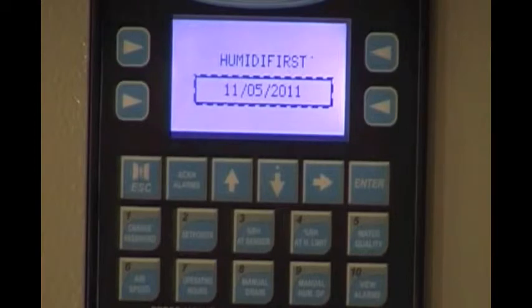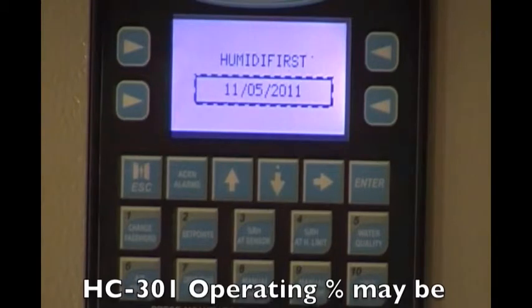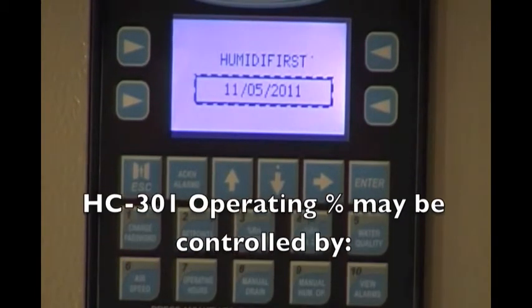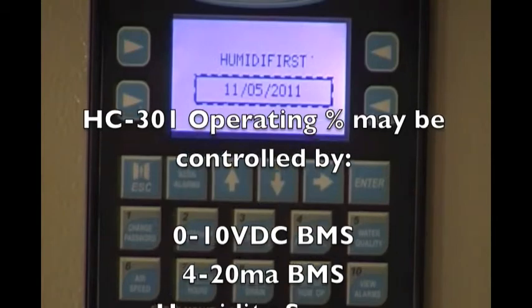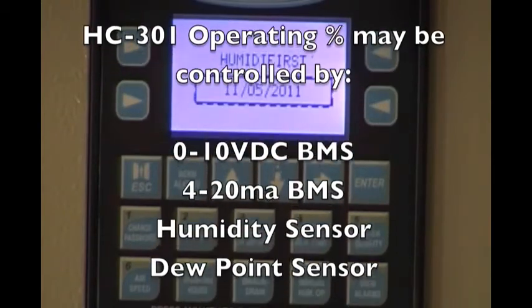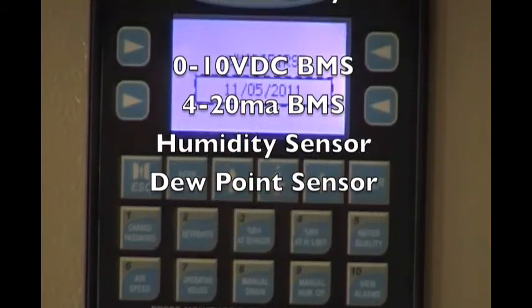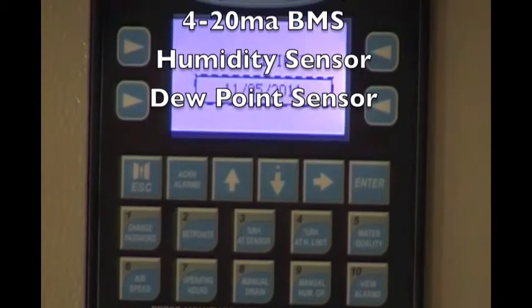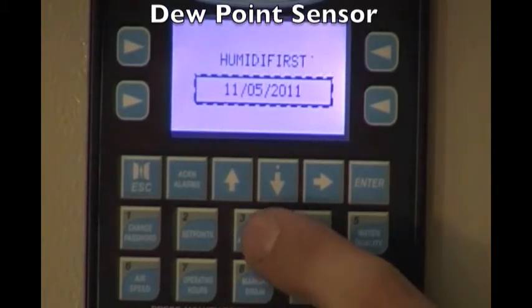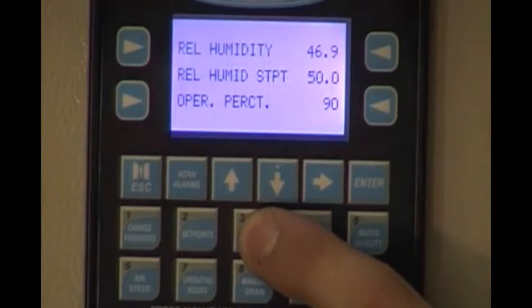Button number 3 is your system's operating percent. This screen will vary slightly depending on your specific application. The HC-301 microprocessor can utilize various BMS signals, humidity sensors, and dew point sensors. Pressing button number 3 will show your operating percent screen.